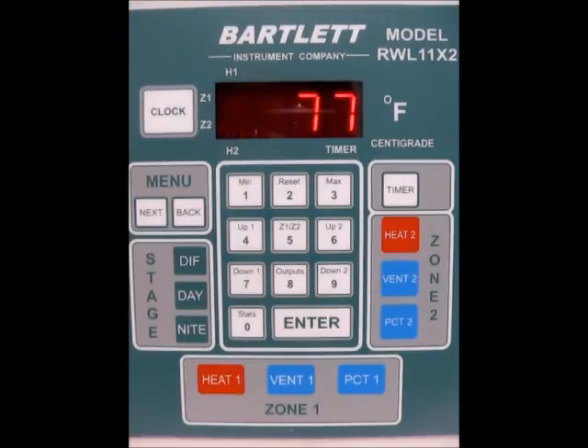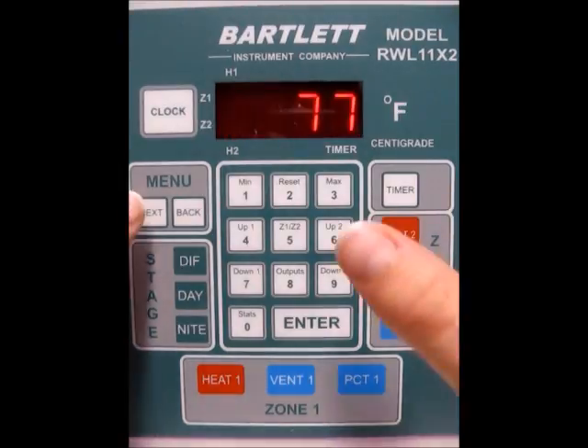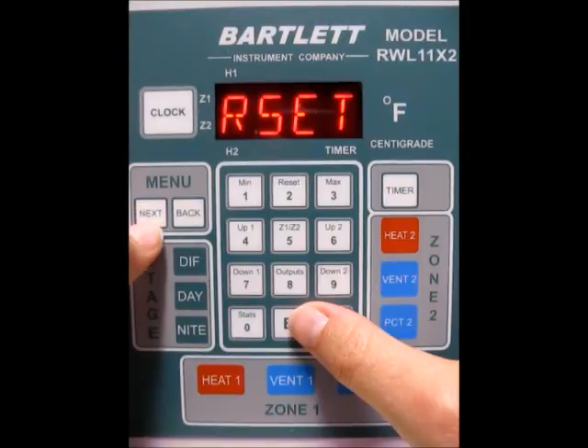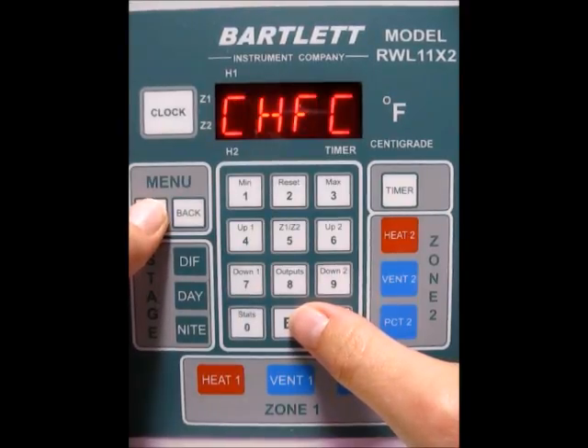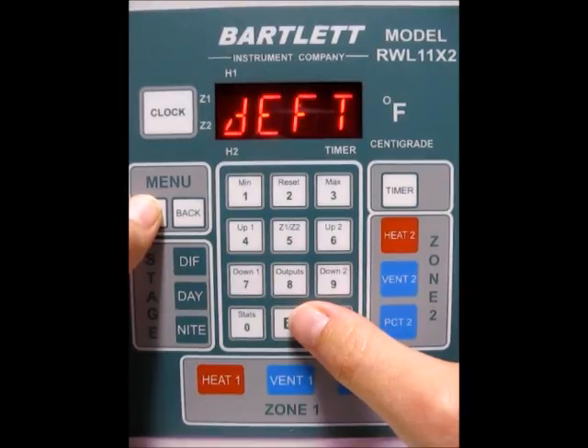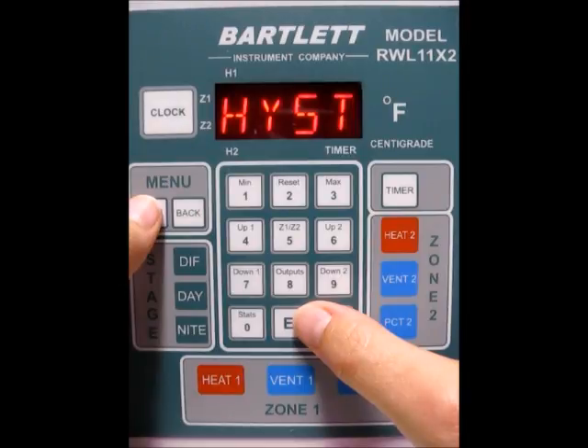Now the next thing we need to do is program our hysteresis. And in PID mode, most of the time, we want a hysteresis of 1. So go ahead and press the next button until HYST is displayed. And then press Enter.